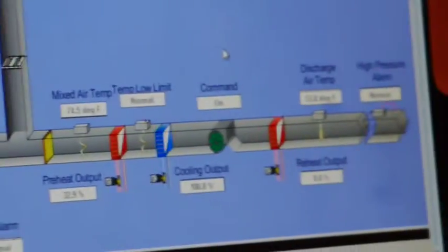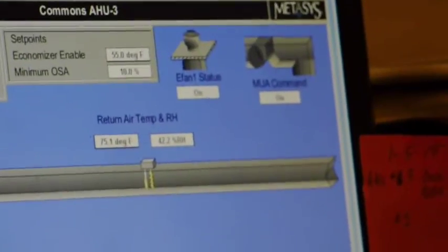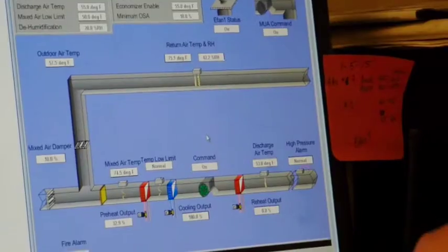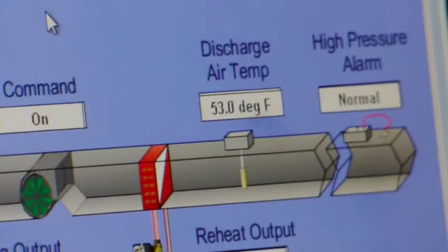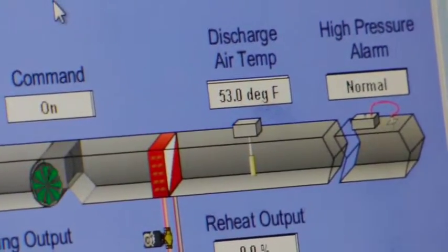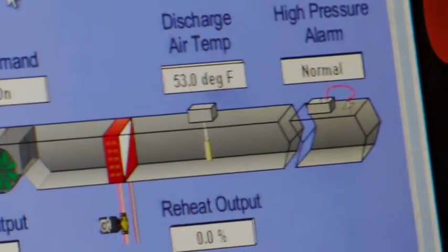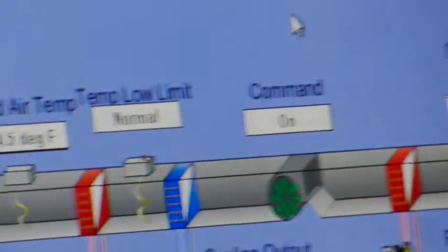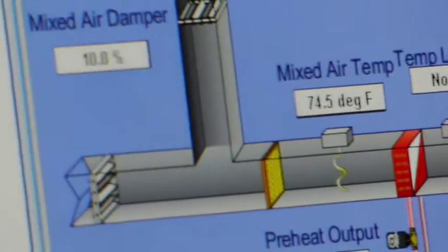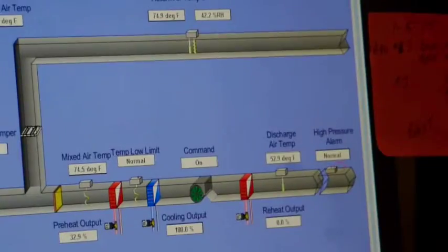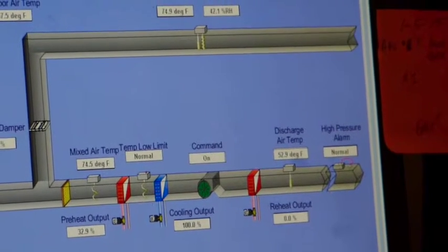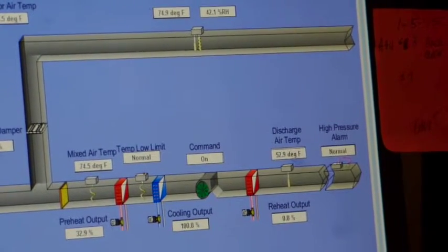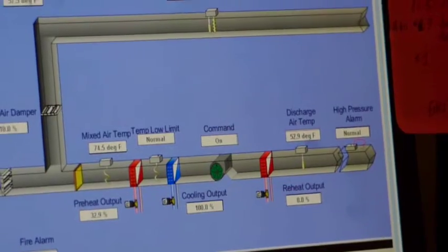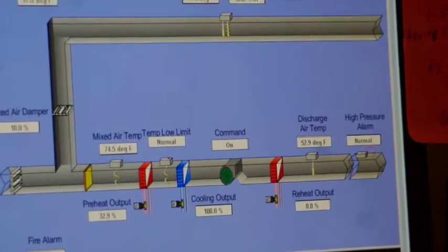To maintain the temperature that we have right now, the discharge air temp of 53 degrees. Okay, so that's what this thing is trying to blow out, because the building evidently is hot today. Must have a lot of heat in the building. So now this unit knows that it's in air conditioning mode. So now that's why it's blowing cool air. So this is basically the building facilities and not our individual rooms. No, it is not. These air handlers here are not.